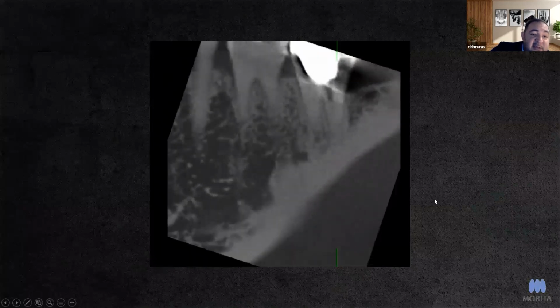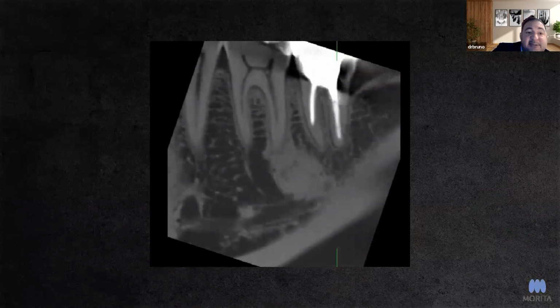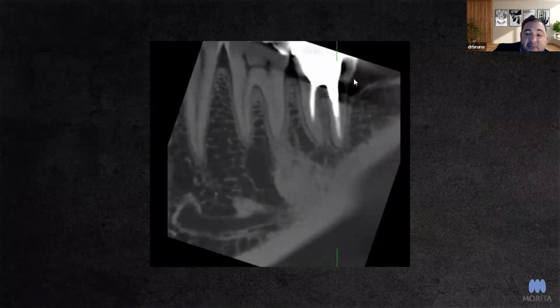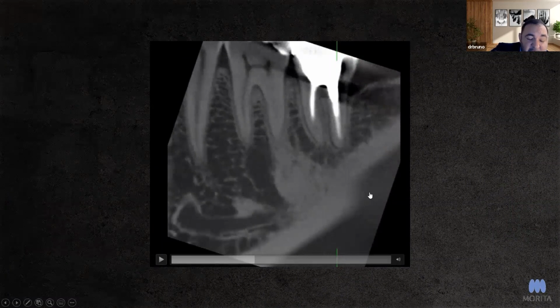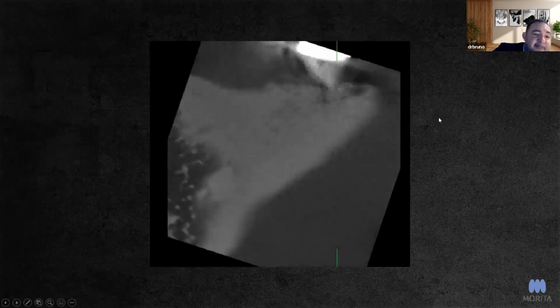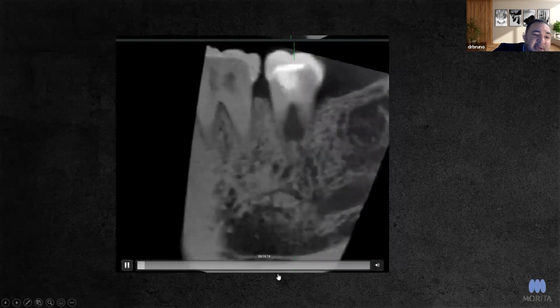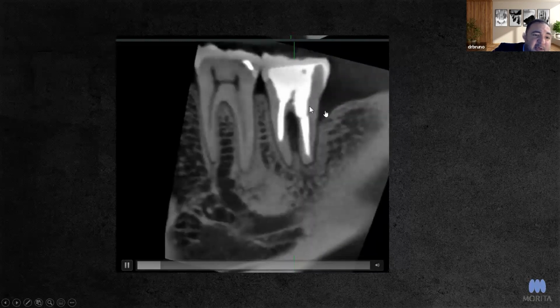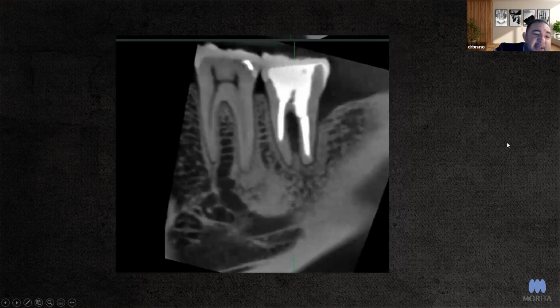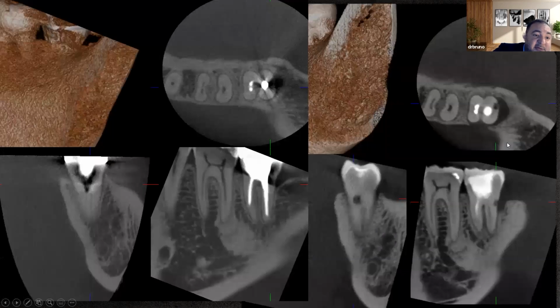For those who are thinking about upgrading your R100 to the X800, what is the basic difference? The basic difference between those two units is that the X800 has a much better tube head and projection geometry. It's the upgraded version. In situations like this where you have beam hardening, and you compare side by side the same patient, you can see that beam hardening is pretty much all gone. And that is the reason why you should be scanning the patients with high KV, high MA. Difference between the R100 and the X800.